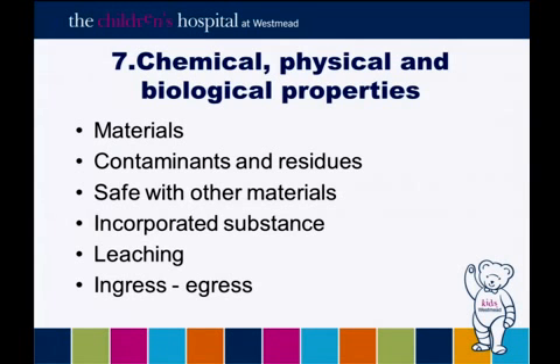And they went, well, we didn't think of that. How are we going to test that? So I said, well, just cut a little bit of the grey tube off and drop it in a bit of anaesthetic agent and see what happens. So they did that once and they came back to me, and they stopped doing it. They went, oh no, it dissolved the plastic. So what was happening was that anaesthetic agent was dissolving into the plastic, which effectively meant that the plastic would then be releasing anaesthetic agent into the circuit, which meant that these anaesthetists had no control over how much anaesthetic agent the patient was getting.